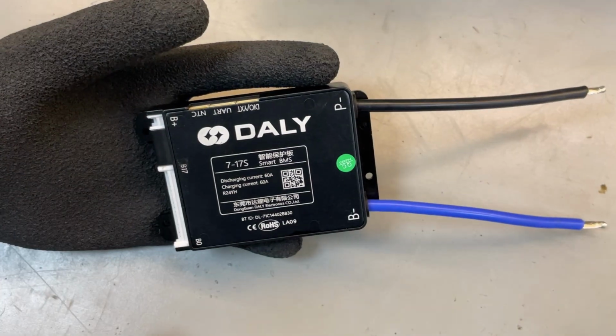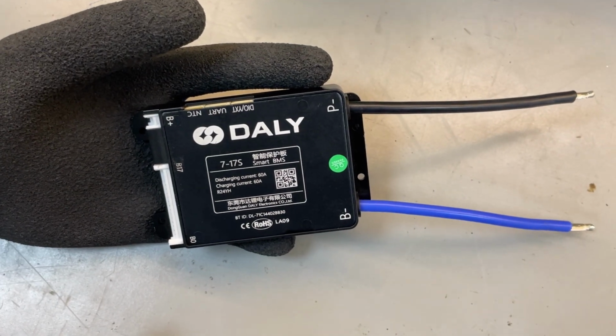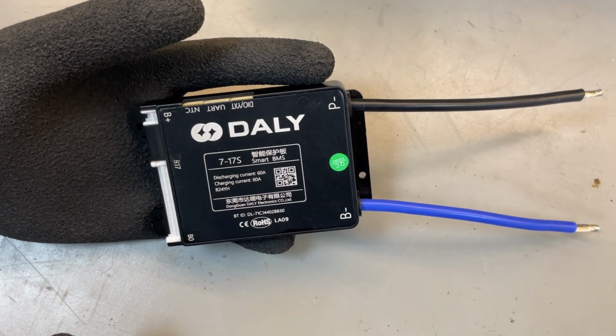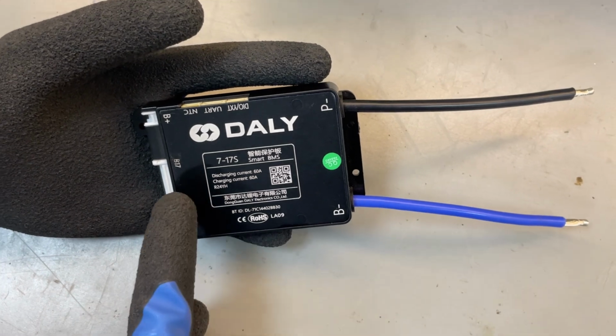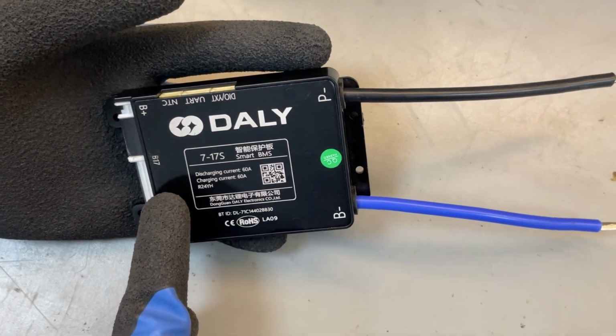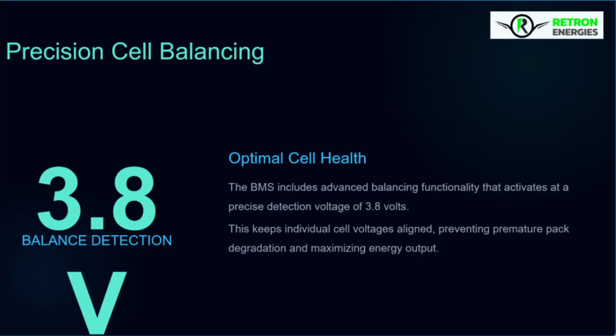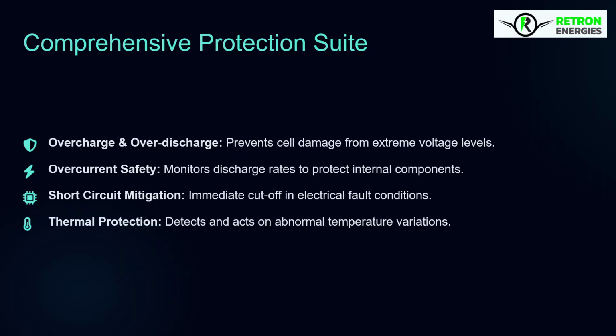It supports a continuous discharge current of 60 amps. The maximum charging voltage supported by this BMS is 71.4 volts. The BMS includes balancing functionality with a balance detection voltage of 3.8 volts. It also provides protection against overcharge, over-discharge, overcurrent, short circuit, and abnormal temperature conditions.